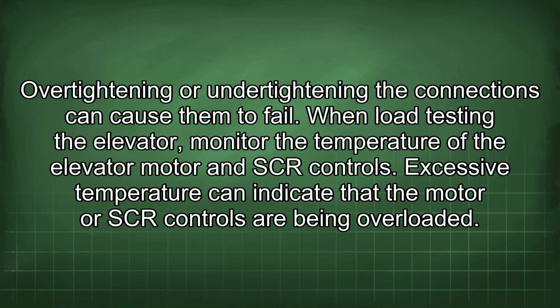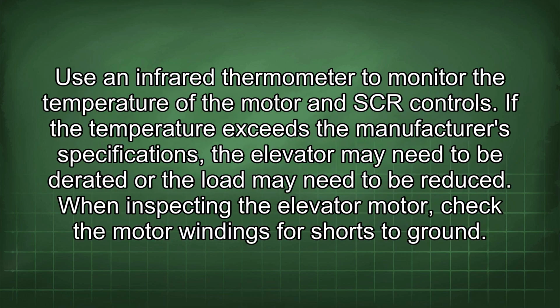When load testing the elevator, monitor the temperature of the elevator motor and SCR controls. Excessive temperature can indicate that the motor or SCR controls are being overloaded. Use an infrared thermometer to monitor the temperature of the motor and SCR controls. If the temperature exceeds the manufacturer's specifications, the elevator may need to be derated or the load may need to be reduced.